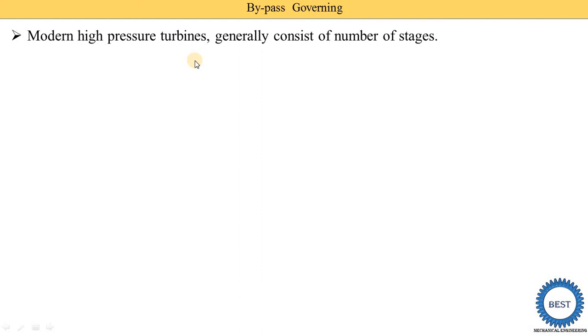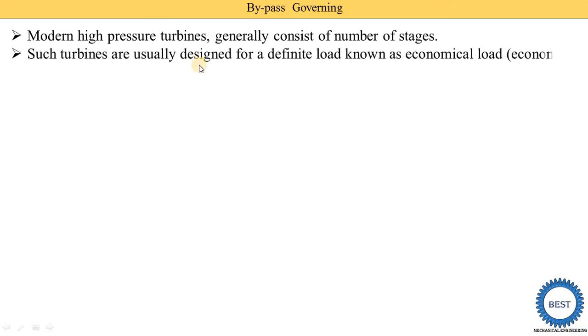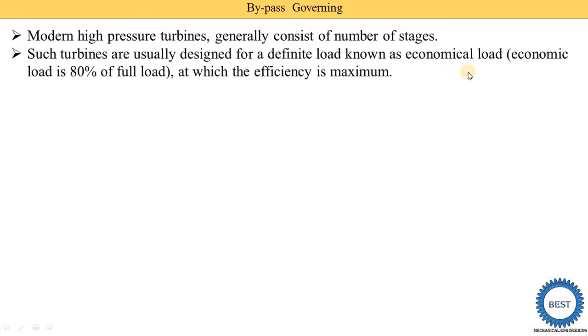In the later stages, more mass of steam is required, and this additional steam is supplied using bypass lines. Such turbines are usually designed for a definite load called the economic load. The economic load is 80 percent of the full load — for example, if the turbine capacity is 10 kilowatts, then 8 kilowatts is the economic load. At the economic load, the turbine has maximum efficiency.